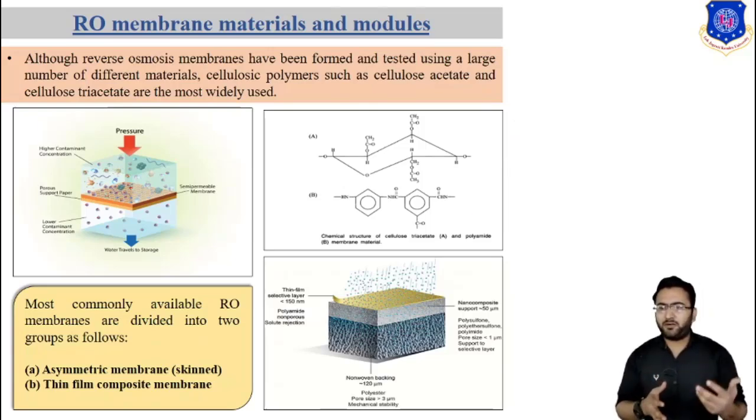They are able to withstand higher temperature and wider pH, from pH 4 to pH 11. But polyamide membranes tend to be less chlorine resistant as compared to cellulose acetate membranes. Solutes which are effectively excluded by the cellulose acetate membrane are NaCl, NaBr, CaCl2, Na2SO4, sucrose and tetraalkyl ammonium salts. These are all rejected by the cellulose acetate membrane, or we can say the reverse osmosis membrane.